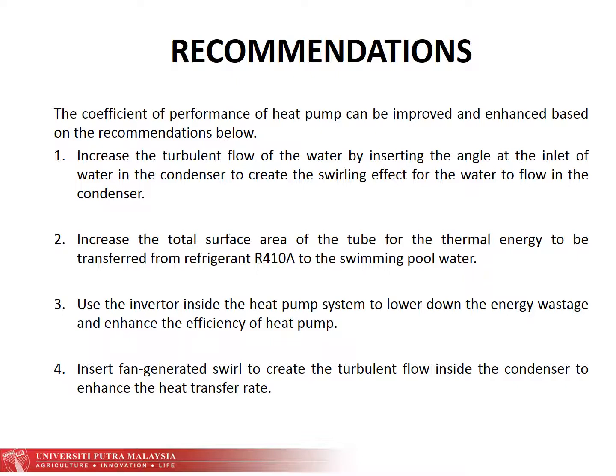Second, increase the total surface area of the tube for the thermal energy to be transferred from the refrigerant R410A to swimming pool water. Third, use an inverter inside the heat pump system to lower energy wastage and enhance the efficiency of the heat pump. Fourth, insert a fan to generate swirl to create the turbulent flow inside the condenser to enhance the heat transfer rate.